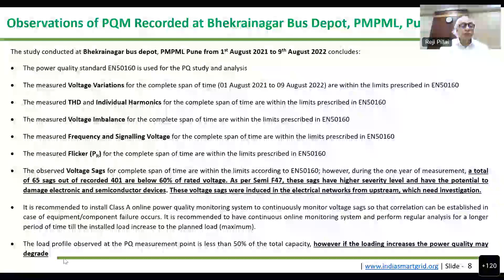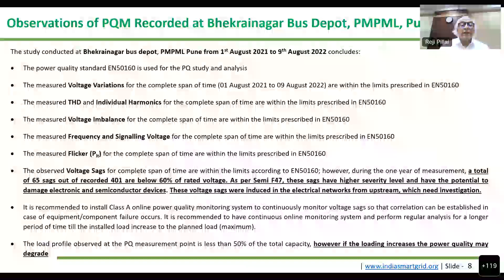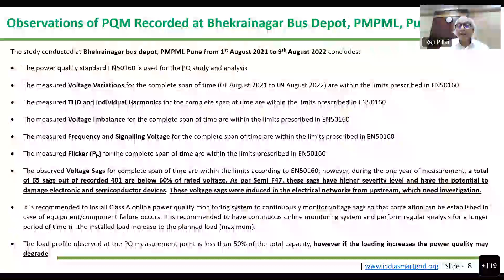It is recommended to install a Class A power quality meter monitoring system in all such large bus depots. We also found that currently the maximum load in this depot, Bhekrainagar depot, is less than 50% of the capacity. If the charging load increases substantially beyond the 58 plus 5 chargers which I mentioned, there could be issues on power quality, which are not there as of now, which is good news.